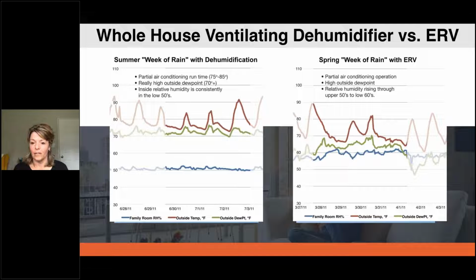We ended up taking out that ERV and putting in its place a ventilating dehumidifier, which you can see on the left-hand side here. Set it to 50–55% relative humidity, and we don't really care what the dew point is outside. We're just going to control the relative humidity in that space to the desired set point.